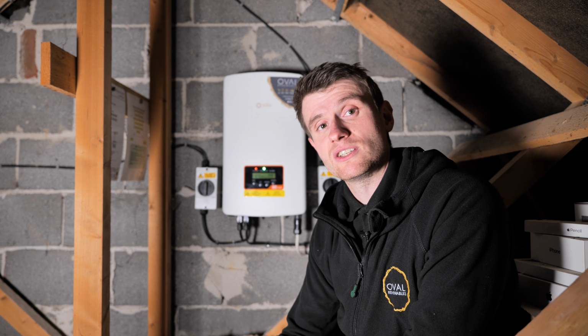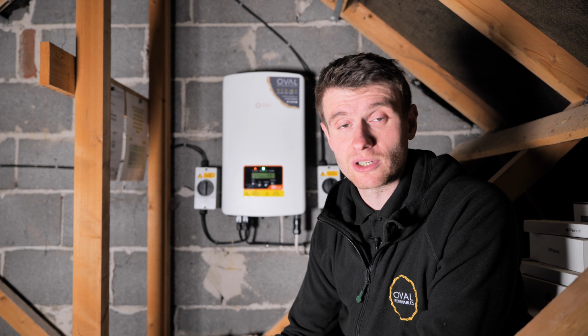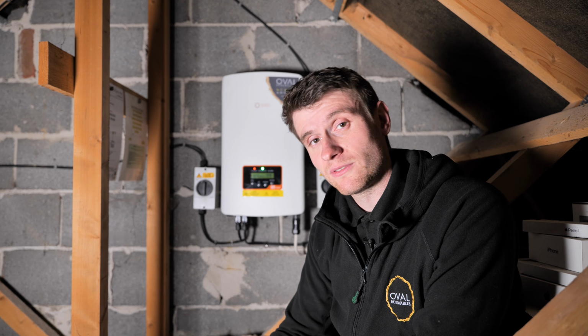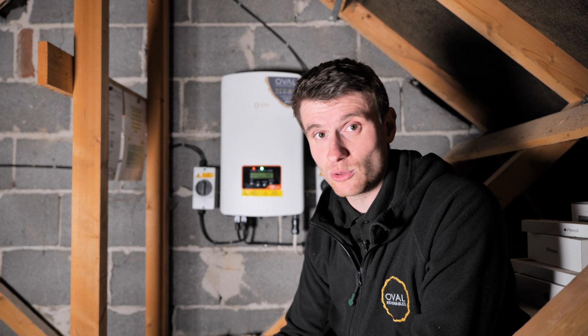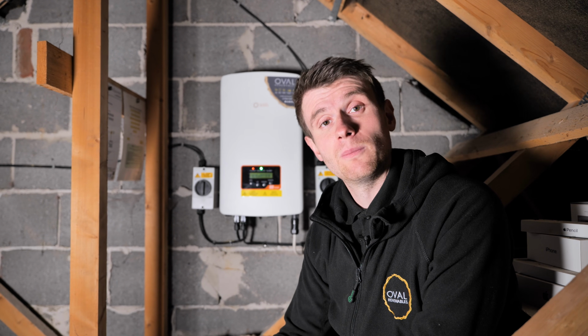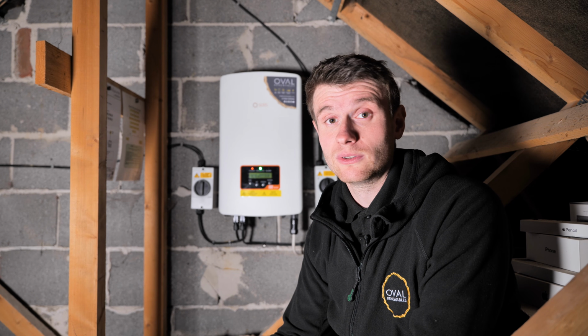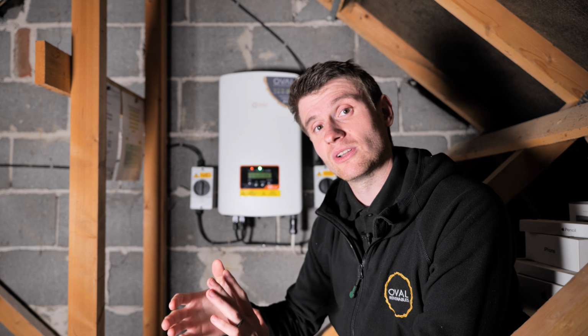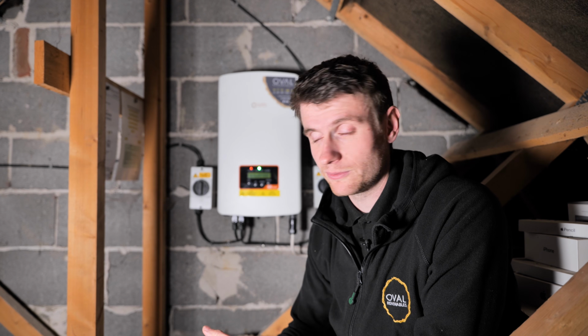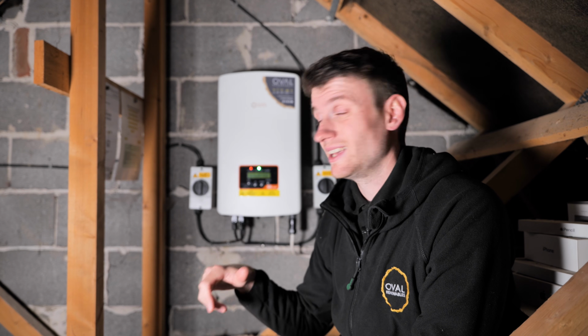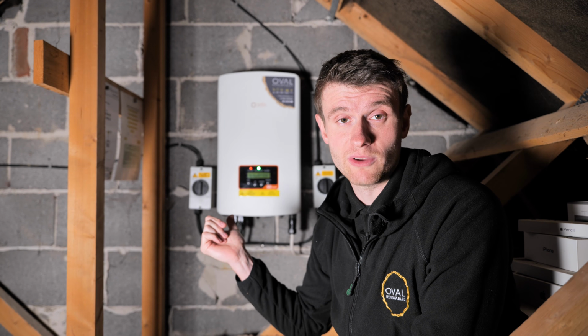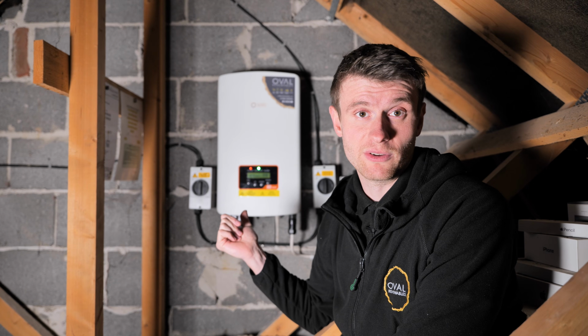For example, we've had situations where some panels have been damaged. These are probably 250 watt panels out here, and it's very hard to find 250 watt panels nowadays, but you could get a 500 watt panel and remove two of the panels, so you've still got the same kilowatt peak on the roof. Same with the inverter - the original was a 3.6 kilowatt inverter, and this is a 3.6 kilowatt inverter.